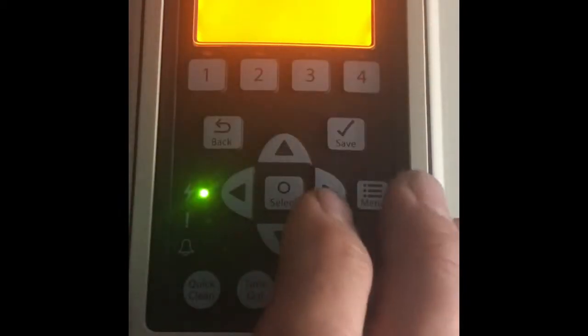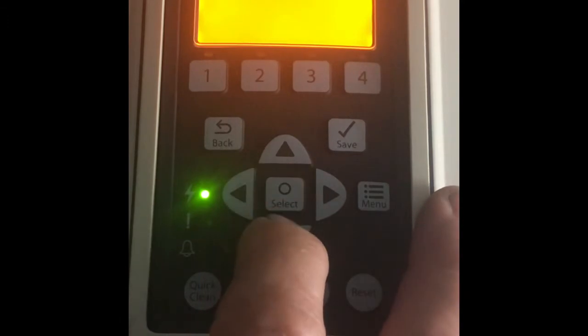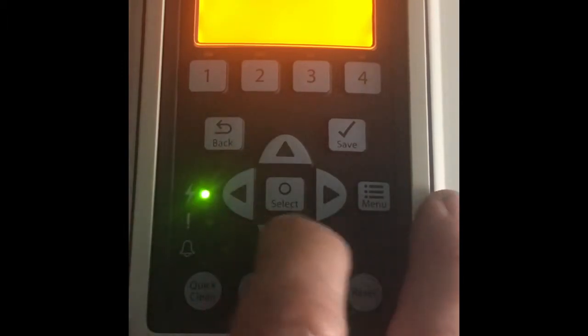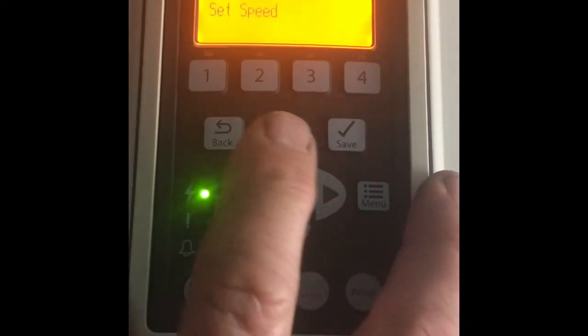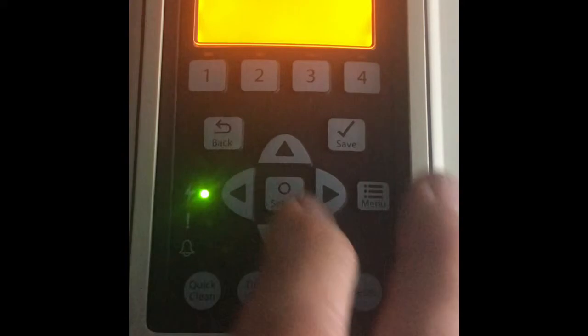We're going to go down to external control, as if you have like a solar controller that you want to incorporate into the pump, where the solar controller will tell the pump that the solar valve has opened and you need to have a higher RPM. So if you hit select, you can see that program 1 is 950 RPM, program 2 is 1500 RPM, and so forth. And you've got 3 programs that you can choose from in order to have that function capability. So right now we're going to go back, external control.